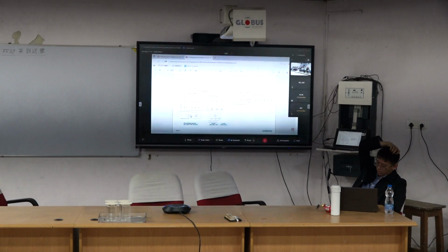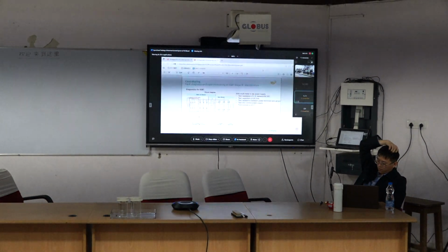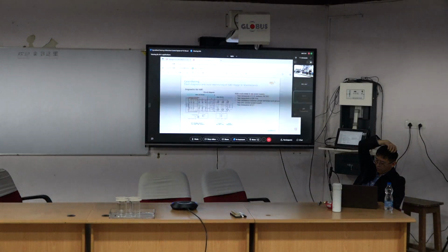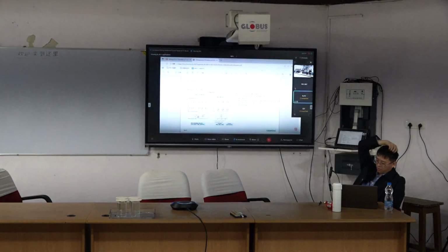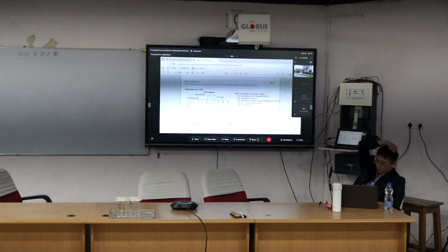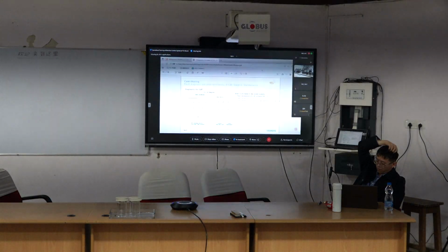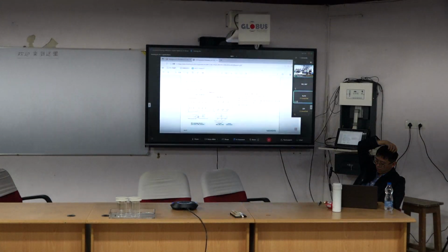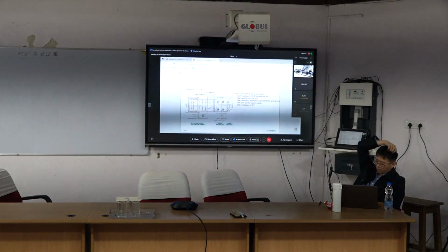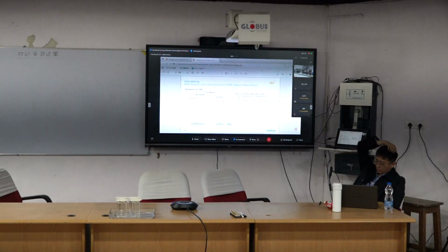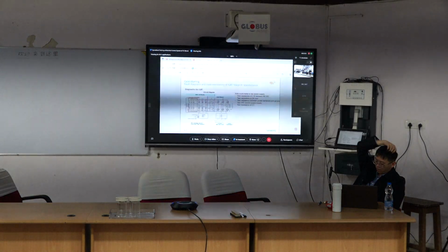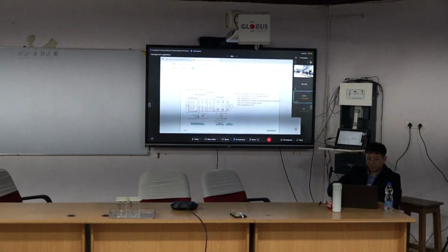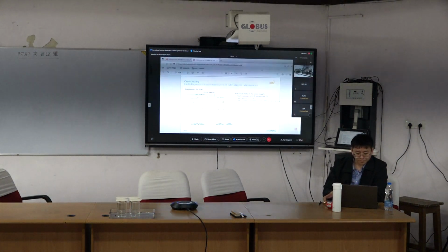Test the control power supply 24 V. You can test the resistance of the CT. Okay, this is very useful, but it's not completely effective. These are just additional tools to assist you in identifying what fault happened.